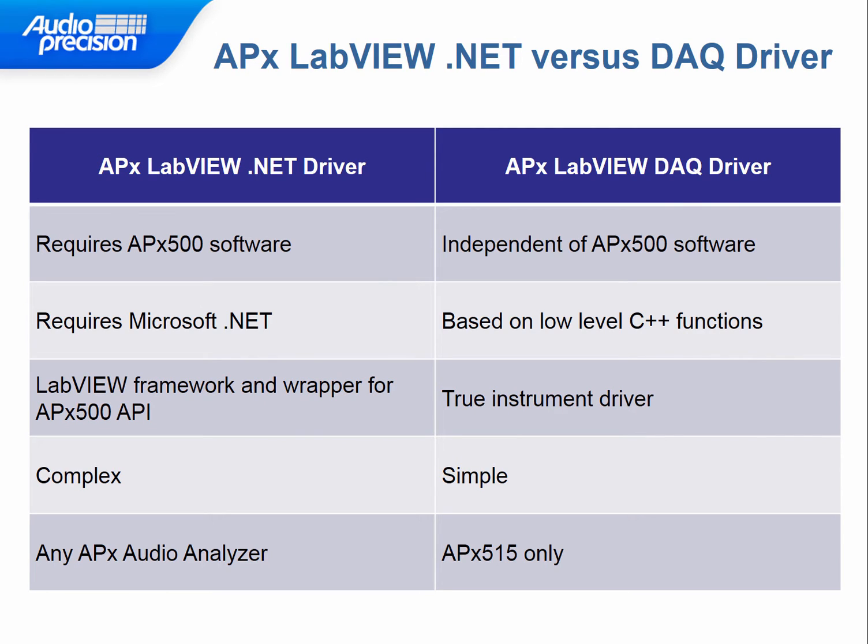This table shows a comparison of the two LabVIEW drivers. On the left we have the APx LabVIEW .NET driver. As I mentioned, it requires the APx500 software. The APx LabVIEW DAQ driver on the right is completely independent of the APx500 software. The .NET driver, of course, requires Microsoft .NET, whereas the DAQ driver is based on low-level C++ functions. The .NET driver provides a LabVIEW framework and a wrapper for much of the APx500 API, whereas the DAQ driver is a true instrument driver.